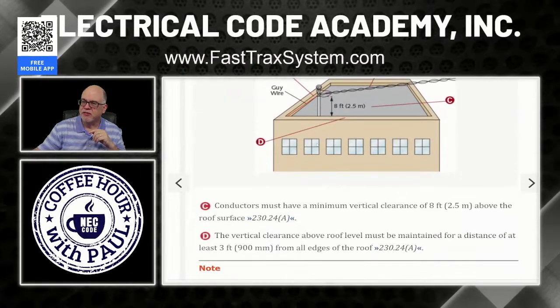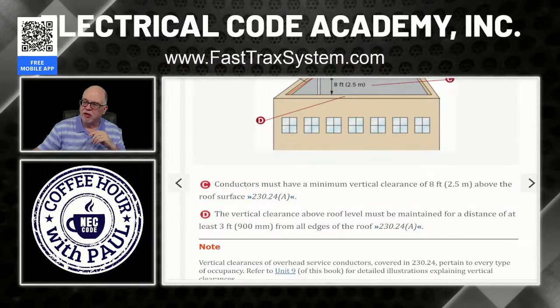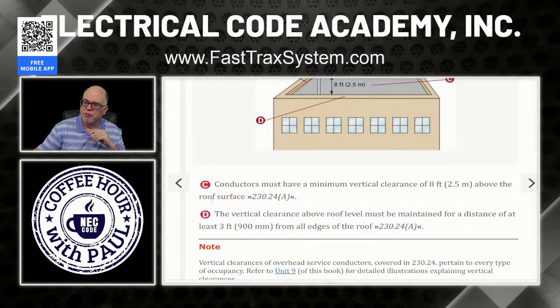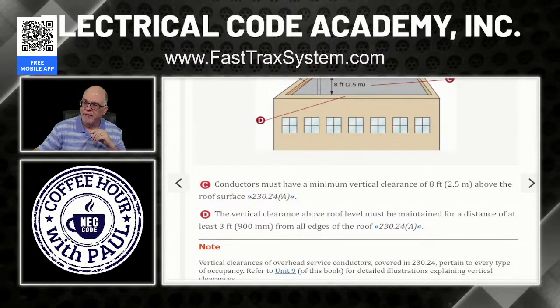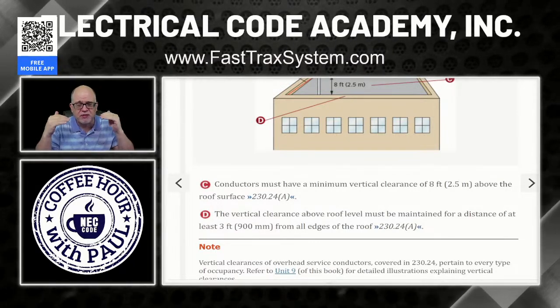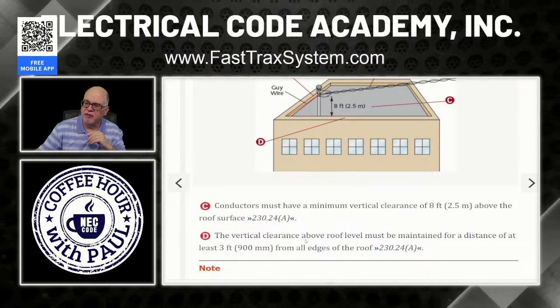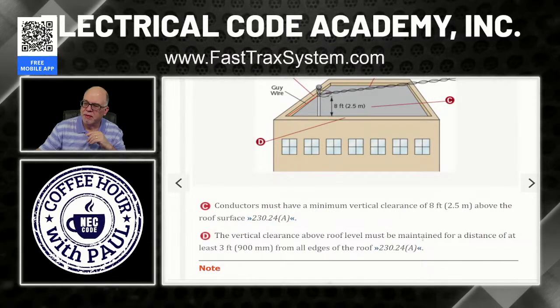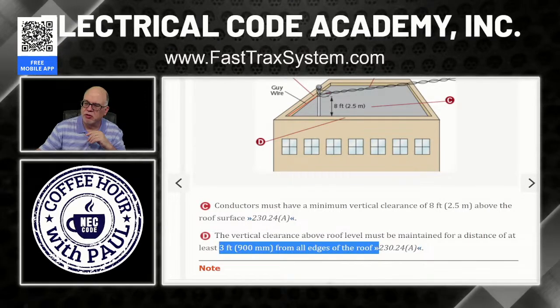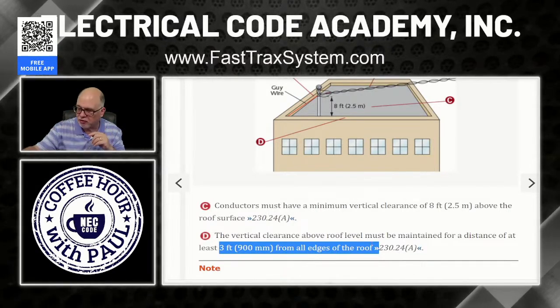All right. Now let's look at C. What is C pointing out right here? Okay. Right here. Just what we just did. Conductors must have a minimum clearance of 8 feet above the roof surface. All right. Also, where does this apply? Is it just above the surface? So that's when we got to look at D. D, it says the vertical clearance above roof level must be maintained for a distance of at least 3 feet from all edges of the roof. Okay, now that's covered in 230.24(A). Okay, we saw that, but we didn't go that far. So let's go on and finish that off.